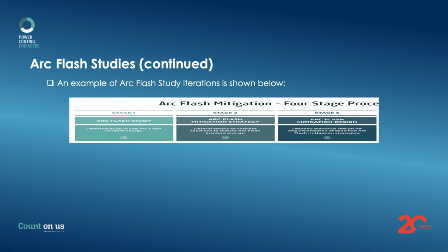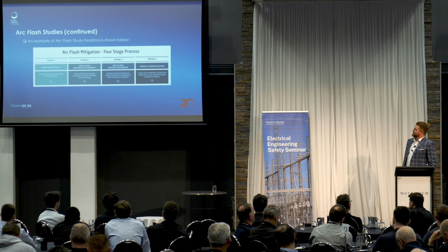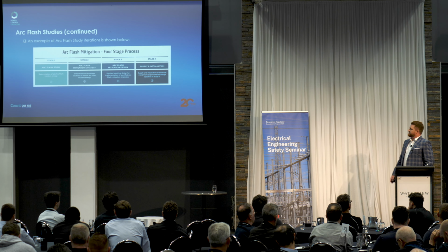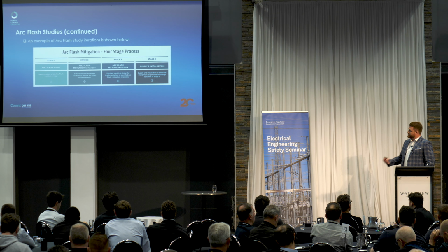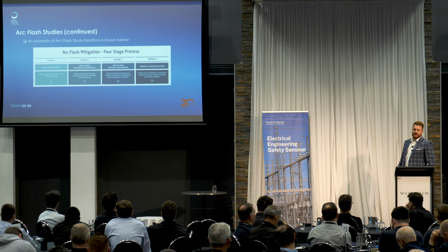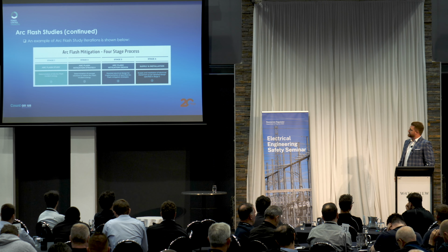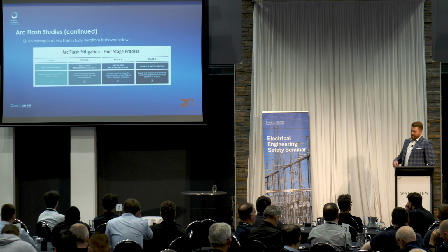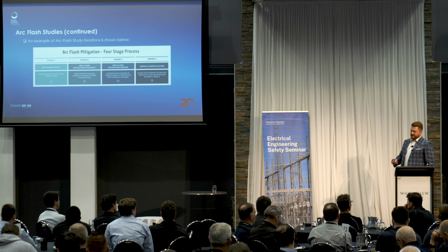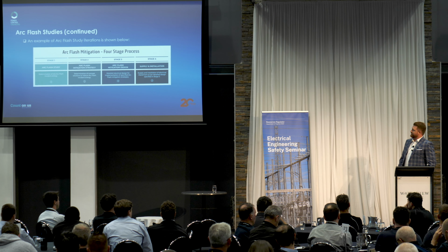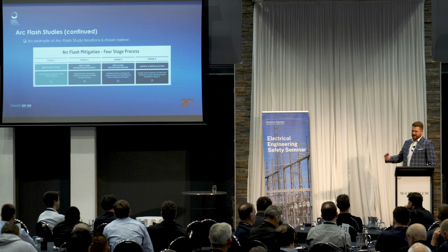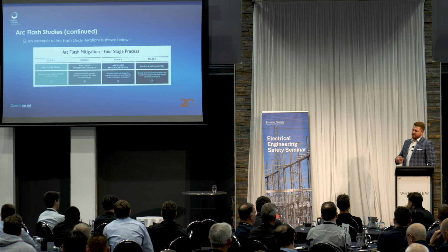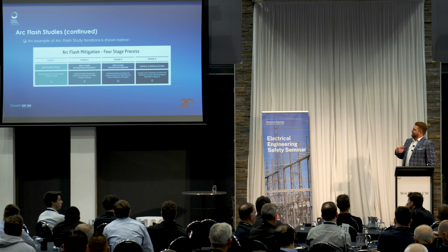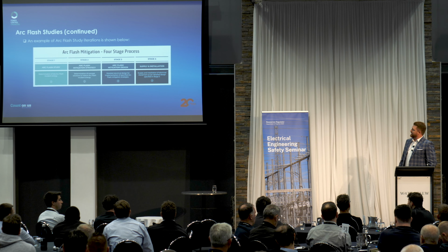So up here is an example of what that process would be. In the first step, you do your initial baseline arc flash study. That'll tell you what your incident energy levels are at all locations. Usually once the first one's done, you'll find out where all your problem locations are, depending on the maturity of your organisation. Once you figure out the places where you have found an incident energy level that's higher than what you are willing to accept, it's important to have another go and do some more studies to try and figure out some solutions on what you can do to reduce your incident energy levels.